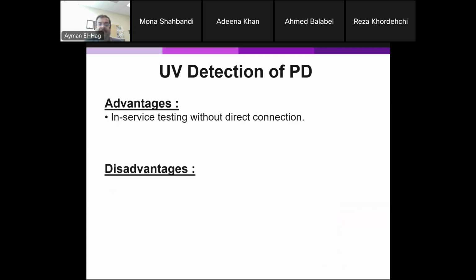The advantages: there's no direct connection. You do it in service, as a regular inspection. This is one of the best techniques for localization because, with the RF antenna, yes, it will tell you that there is a defect in that direction, but where is it exactly? You don't know exactly. But with the UV camera, you can see the defect yourself, of course, if it is external. It has very good location accuracy, and it is, of course, a very safe method.